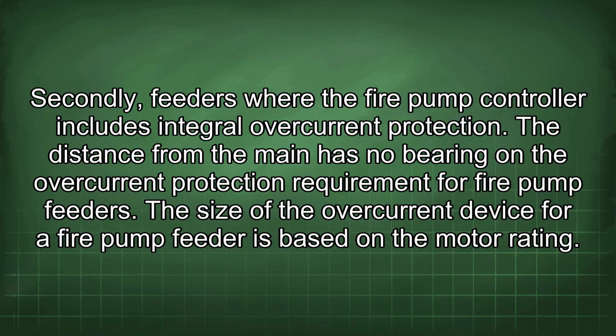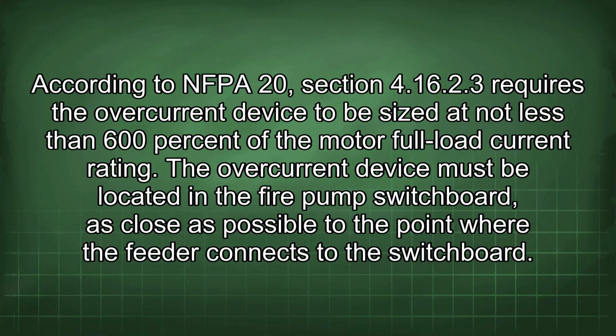The distance from the main has no bearing on the overcurrent protection requirement for fire pump feeders. The size of the overcurrent device for a fire pump feeder is based on the motor rating. According to NFPA 20, Section 4.16.2.3 requires the overcurrent device to be sized at not less than 600% of the motor full load current rating. The overcurrent device must be located in the fire pump switchboard as close as possible to the point where the feeder connects to the switchboard.